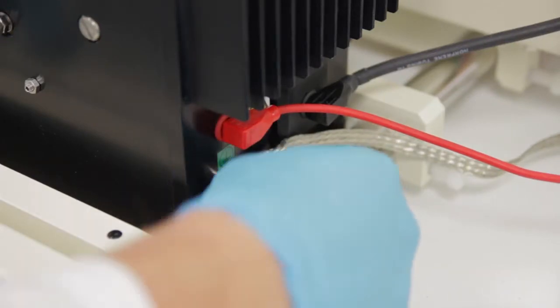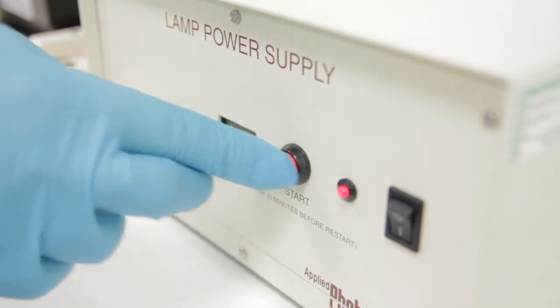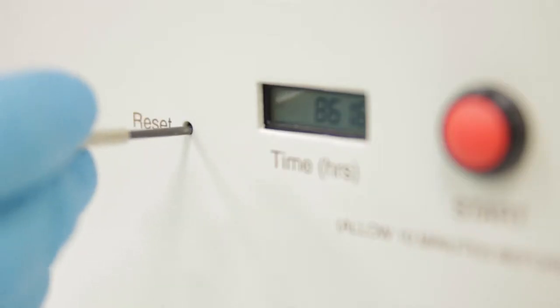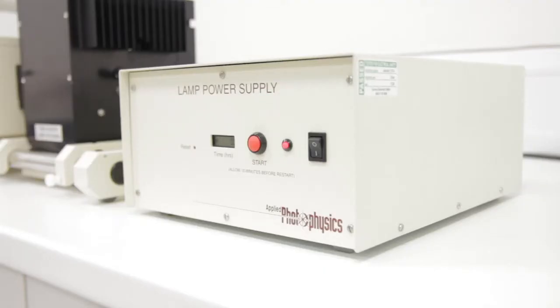Switch on the lamp power supply. Wait 10 to 30 seconds then ignite the lamp. If applicable, reset the LCD counter on the power supply. Leave the lamp to equilibrate for 30 minutes.